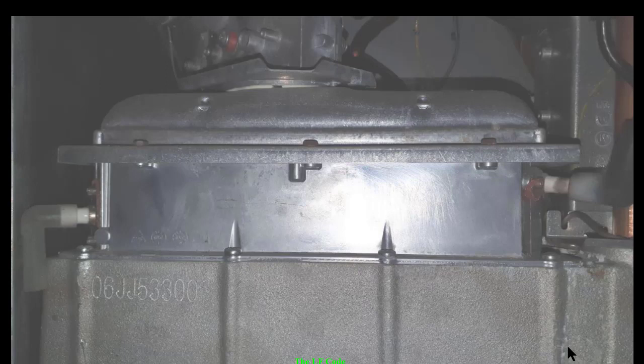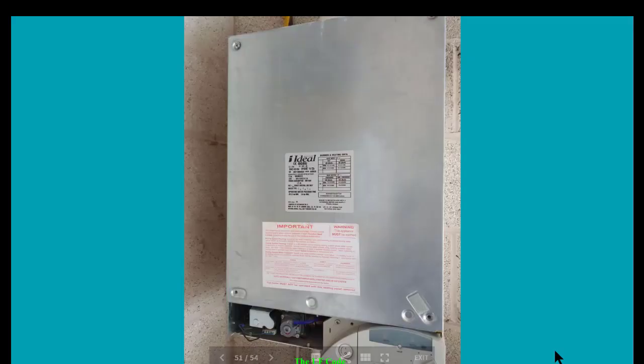And as I said, once you've checked all of them, if they are okay, also we've done the flame sensing lead as well. Now if that was all good and you were still getting the same fault, then as I said, the last thing would be the insulation pads inside the burner area. They would have failed, and then you'd have to take the burner, the fan out, the burner cover off, get new panels and replace them, because that's what would be causing a problem.